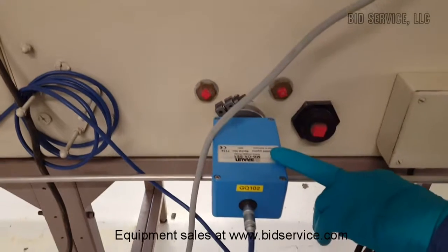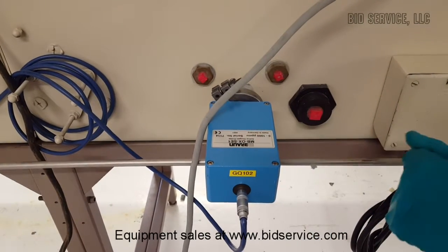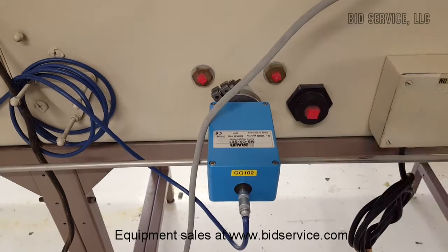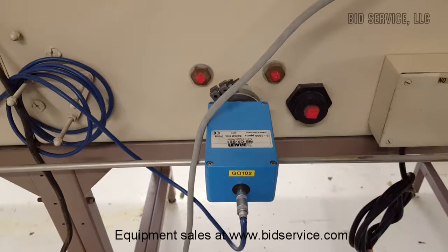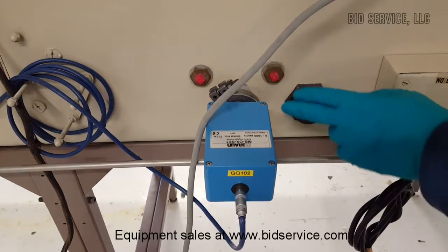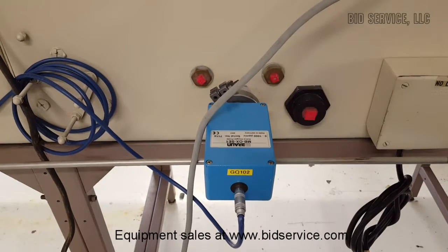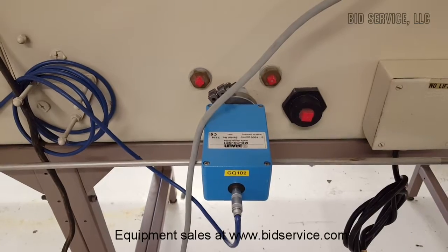Down here you can see we have our oxygen sensor, which is the Braun MB-OX-SE1 — it's just inside the box. This is our house oxygen sensor; we just use that here to qualify the glove box. I'll pull this out prior to shipping and blank it off with a KF40 blank-off.